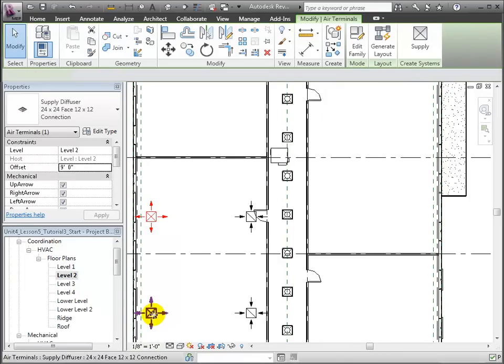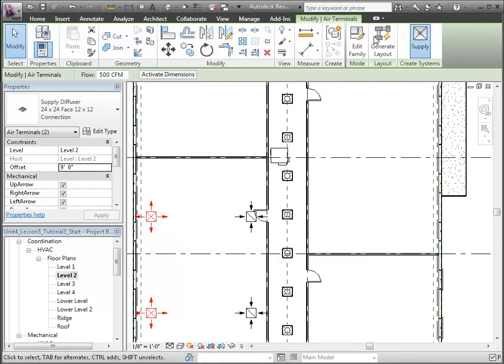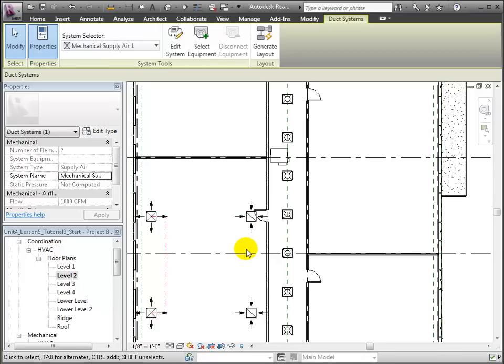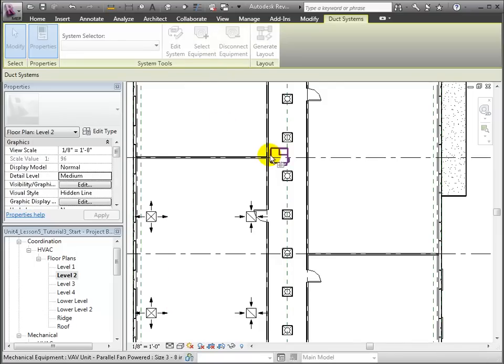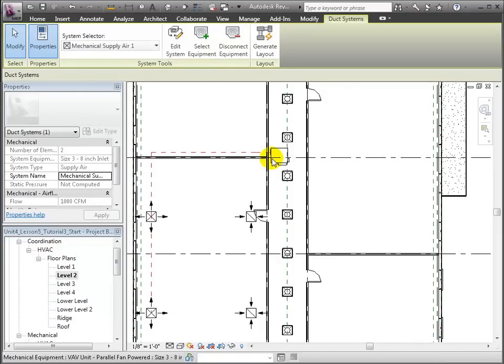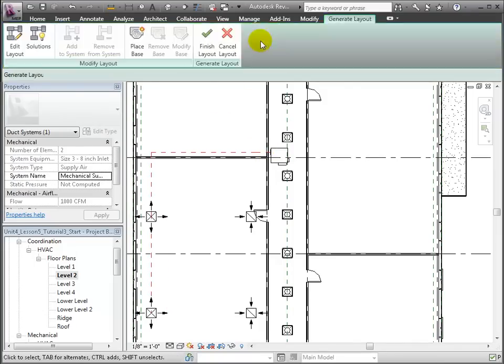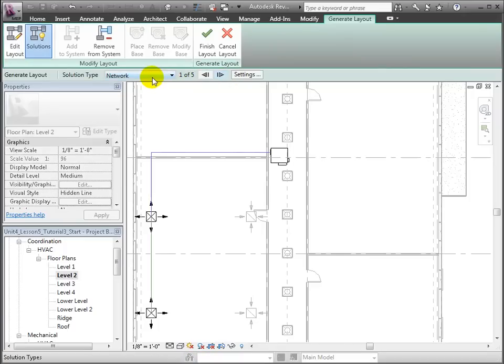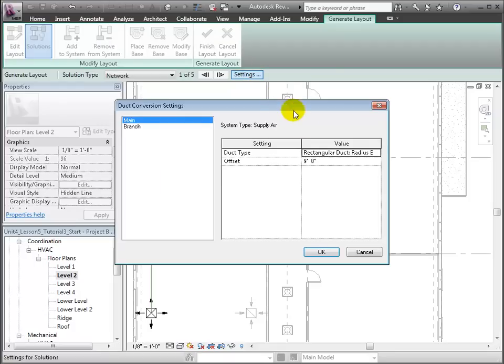The Modify Terminals tab appears and we can choose to create a new supply system for these terminals. The Duct Systems tab appears with options for editing the system. First choose Select Equipment and click on the Air Handling Unit. Now open the Generate Layout tool. We will keep the Network option, but let's open Settings to define the types and offsets for the main and branch of this ductwork.